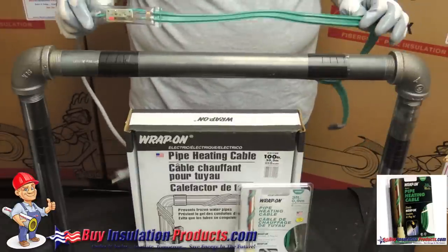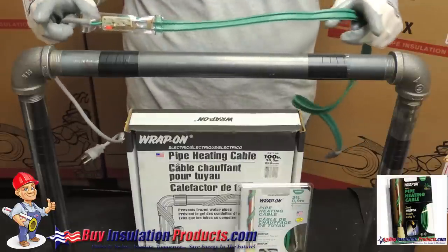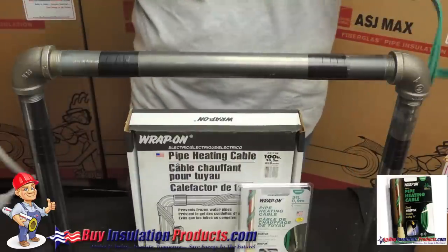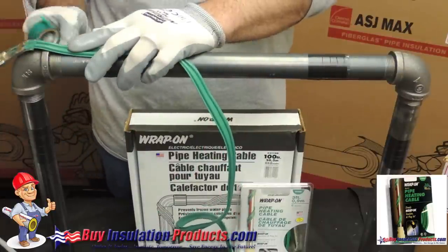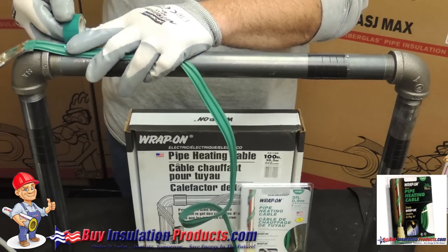One thing to remember when installing a pipe heating cable is that the thermostat has to be left outside of the pipe insulation. So for this mock up we are going to heat trace this piece of pipe and put a piece of pipe covering here. So let's put the thermostat outside of that area. There we go.